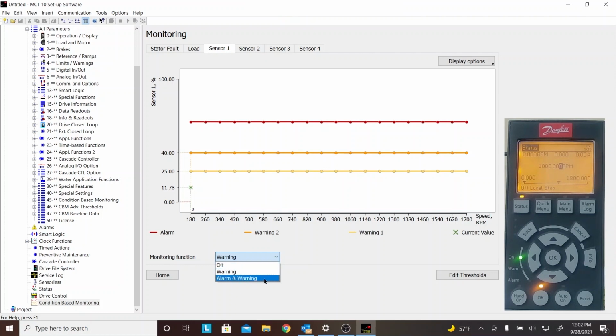Now, they may be off like the other ones, or they may be alarm and warning. One thing to note about alarm and warning: if you are in alarm and warning and you do end up over this warning area here, you will trip the drive. So that could be a problem, or you may want that. But keep in mind, if you trip that drive and you're in production, and you don't mean to trip the drive, that might create a real issue for you. So right now I'm going to run the drive.